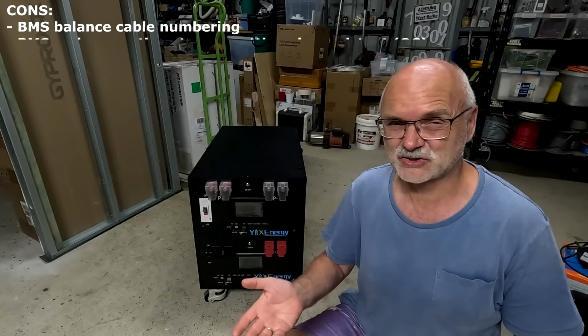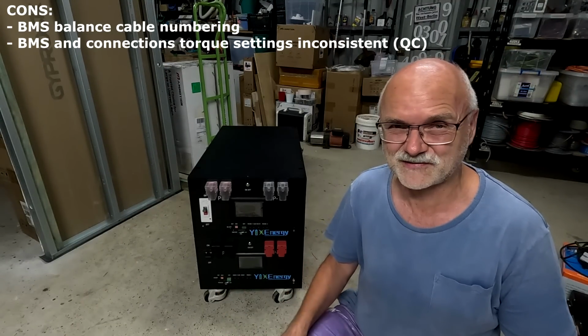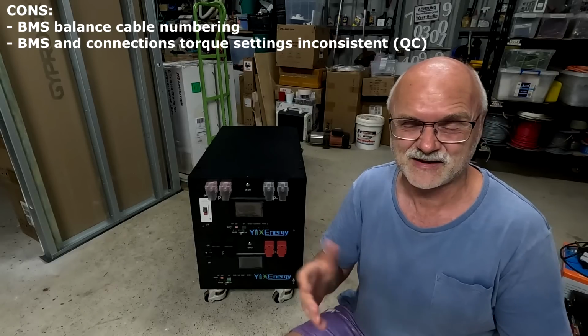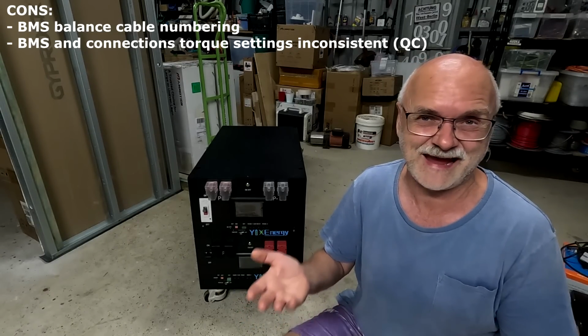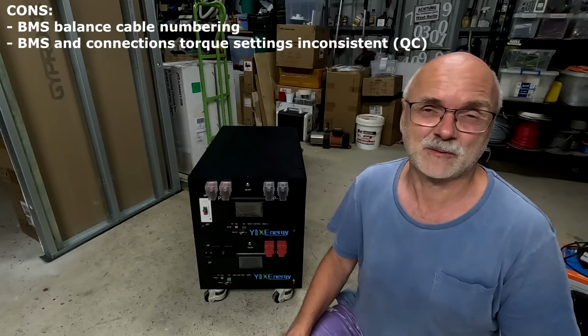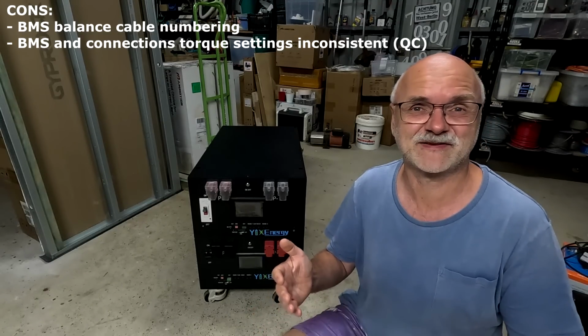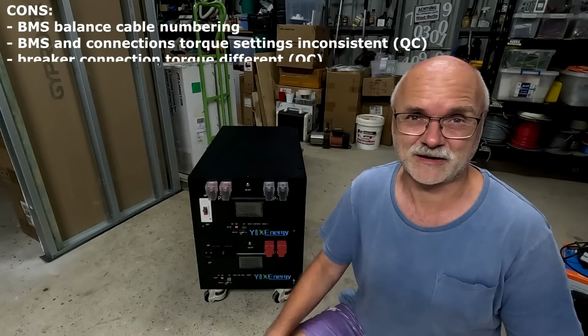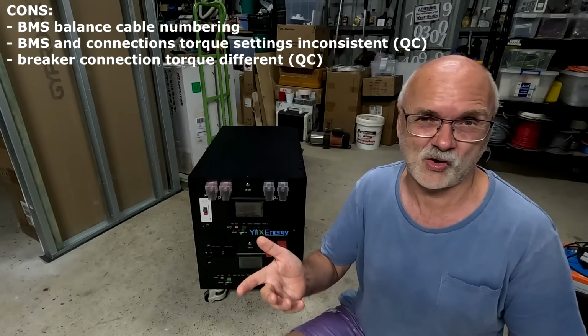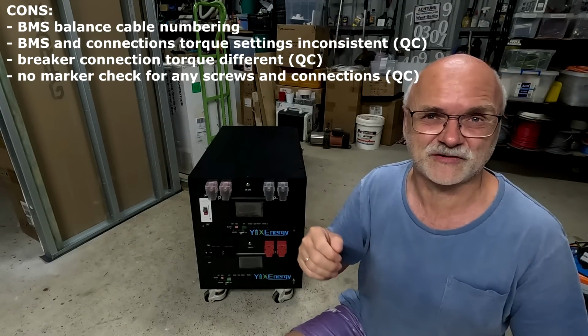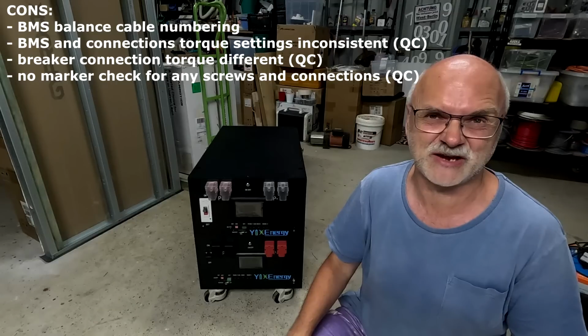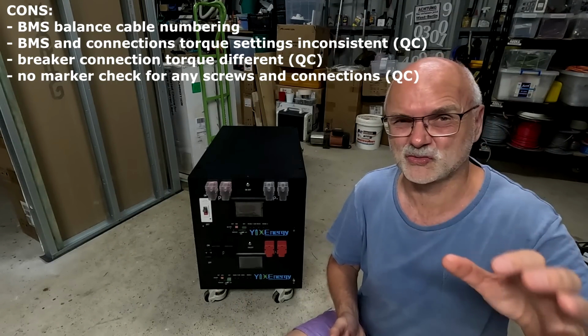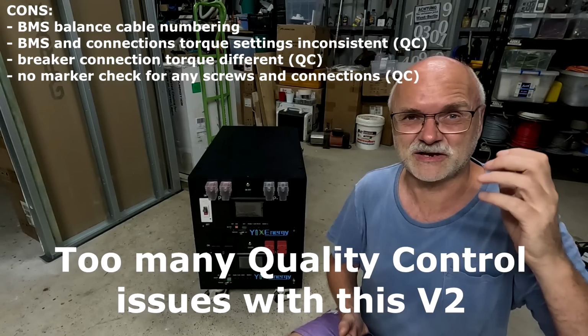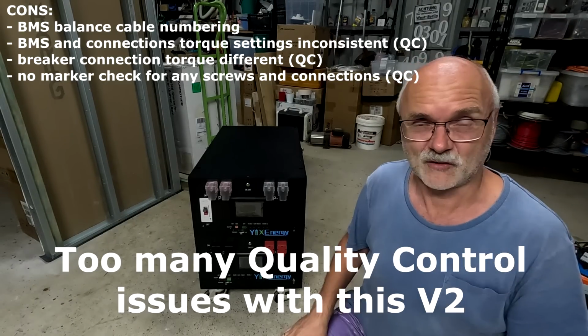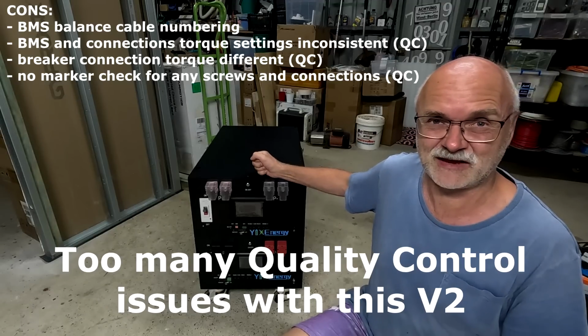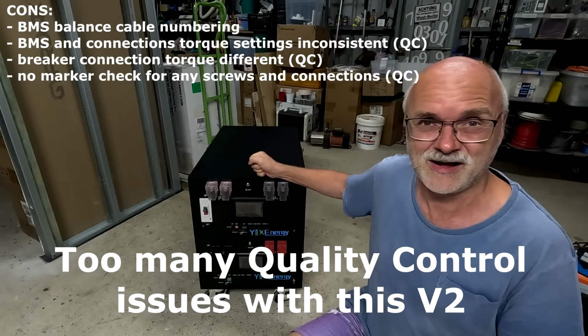The BMS connection torque settings were a bit inconsistent, I could measure different torque settings. Yixiang said they're doing it by hand, not with a machine. Well, if they used a torque wrench, they would all have the same setting, right? Same for the breaker connection, top and bottom had different torque, and there was no marker on any of the screws inside, so we don't know if they've been checked or not. So all these complaints about screws, connections and torque settings, this is actually a quality control issue. It looks like nobody is actually checking the quality of these boxes anymore after they've been built.